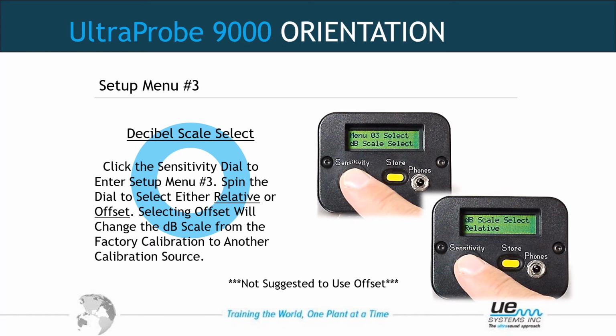Decibel scale select, setup menu number 3. So you will rotate to the right one more time to get to menu number 3. Menu number 3 is dB scale select. Spin the dial to select either relative or offset. Selecting offset will change the dB scale from the factory calibration to another calibration source. Typically, we do not offset these units. If the calibration is off, then changing the dB scale will not help.